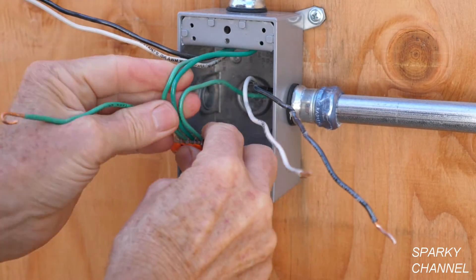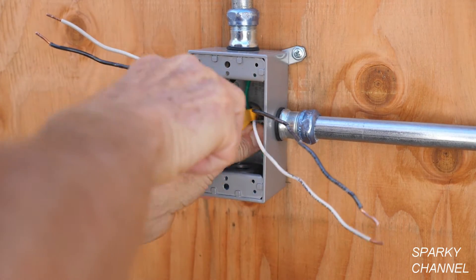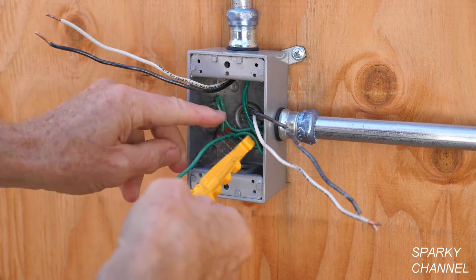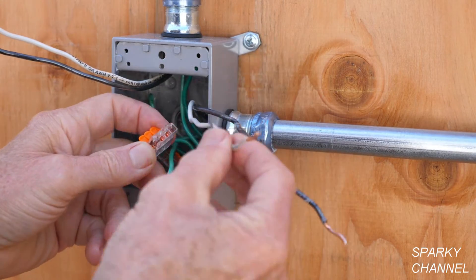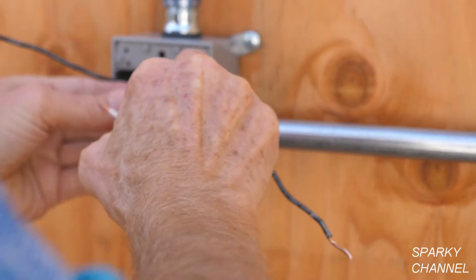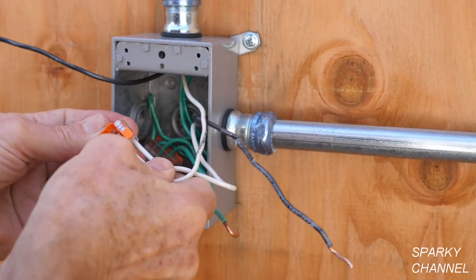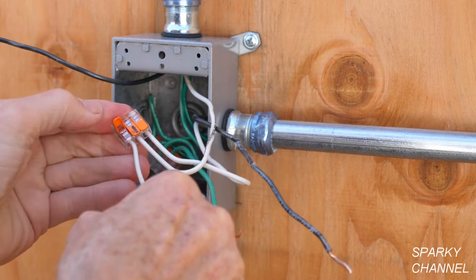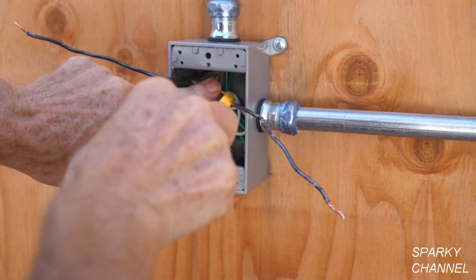Now push this into the back of the box. My friend and master electrician Warren Tarbell invented this tool right here — he calls it the Volt Claw — and you can use it to push the wires back into the back of the box. Now I'm going to prepare the neutral wires using a three-connector Wago lever nut. There's the one that comes from the line cable and this is the one from the load cable — just push it in and click it down. Then I've prepared one neutral pigtail that will go to the device. Push the neutrals into the back of the box.